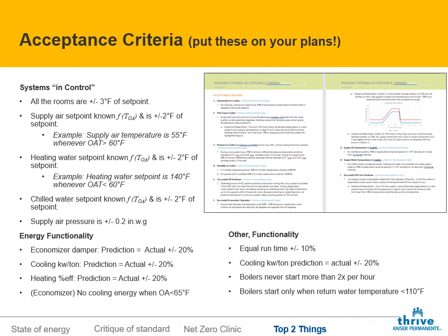And you want to achieve that as a prerequisite, right? Make sure all your systems and all your zones and all your temperatures are in control. That's a perfectly good statement. Your building might be an energy dog, but at least you can say that all your systems are in control. The next tier of acceptance criteria comes with that energy functionality, right? The economizers are supposed to work the way they're supposed to work. The efficiencies should come true the way they're supposed to come true, right?